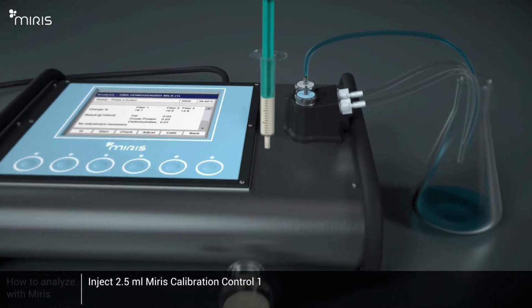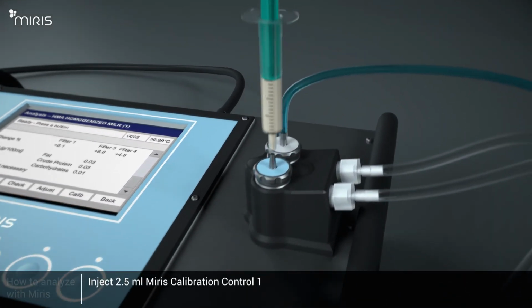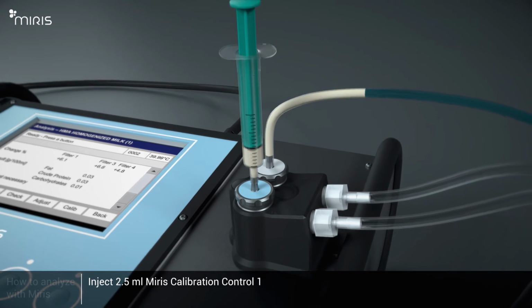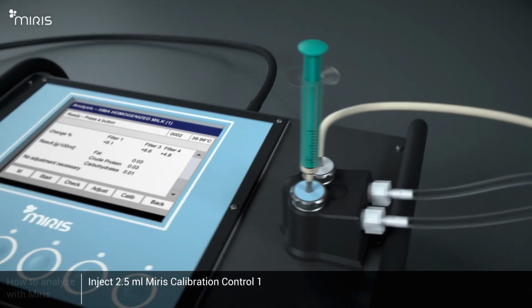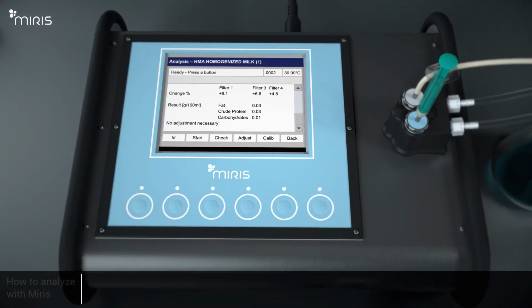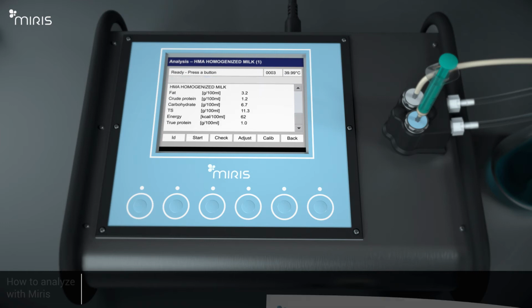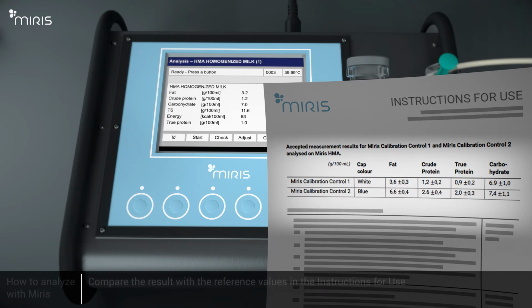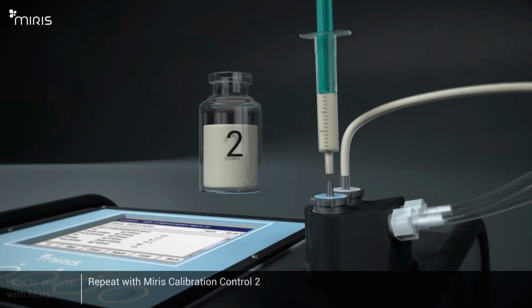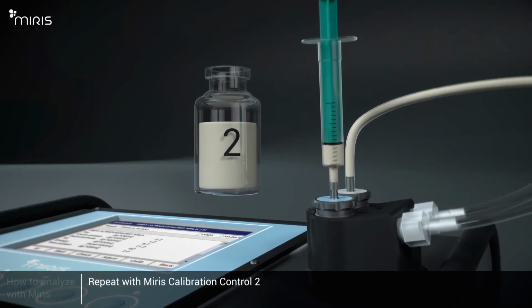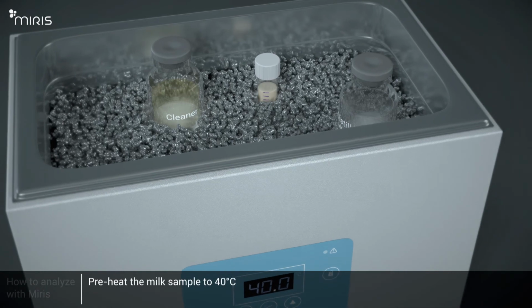Inject 2.5 milliliters Miris Calibration Control 1 and leave about 0.5 milliliters in the syringe. Leave the syringe on the inlet. Select Start to begin the validation. Wait approximately 60 seconds. Compare the Miris Calibration Control result with the reference values. Repeat the validation procedure with Miris Calibration Control 2.